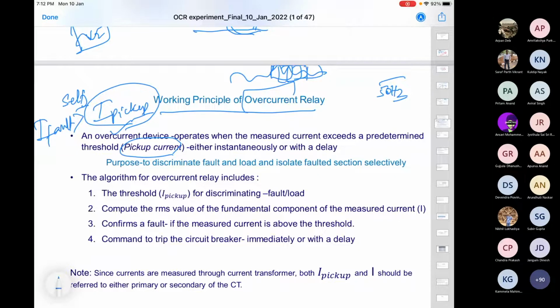Now there are two situations. If the current is high, then should it trip instantaneously or should it delay the process? Now there is a question here. In a distribution system, this delay or instantaneous operation is governed by the same H equals I square RT. Can you delay it or can you not? Now, what are the advantages of delaying? I have understood that the sooner it trips, the better.